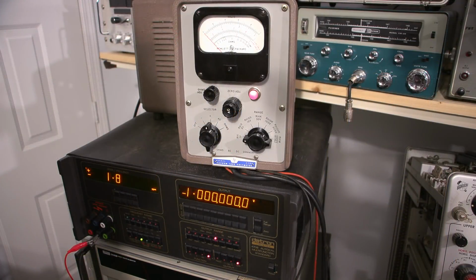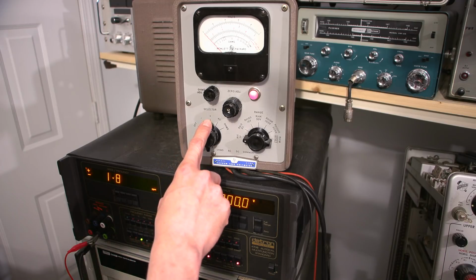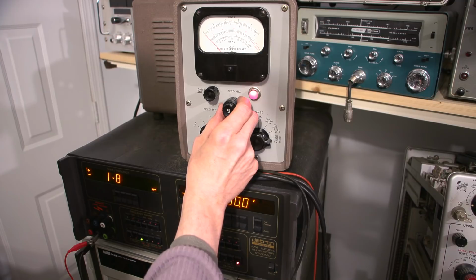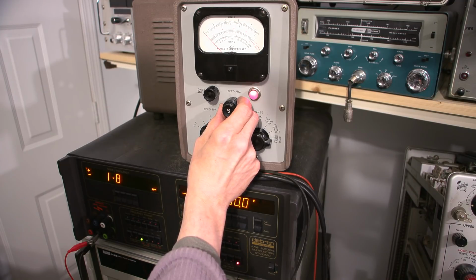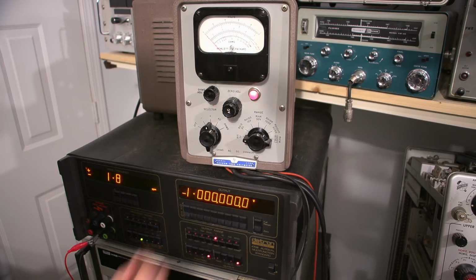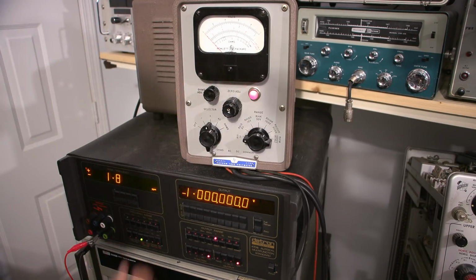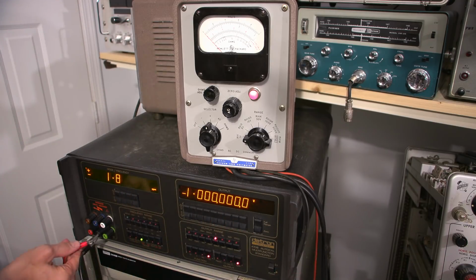The very first thing to do in this calibration procedure is set the 1 volt scale. So that's the DC cal setting. That should be done first. So I have it in positive volts here. I have the leads shorted on the test fixture here, or the calibration fixture. So I'll zero this up. That's pretty close to 0 to my eyes. I'm looking at this straight on. It might look a little bit off to you because you're on a bit of an angle. It's kind of hard to get everything all in here.